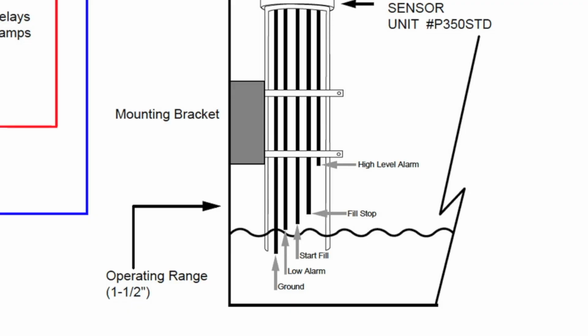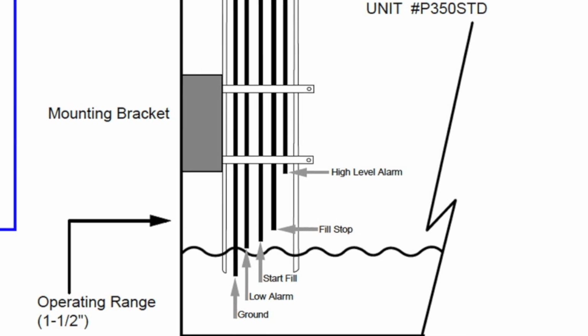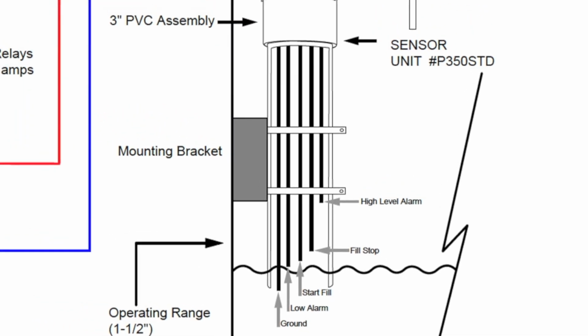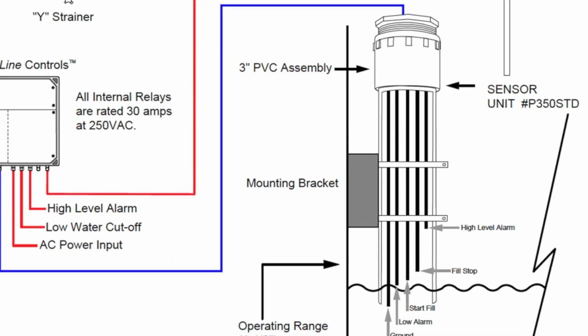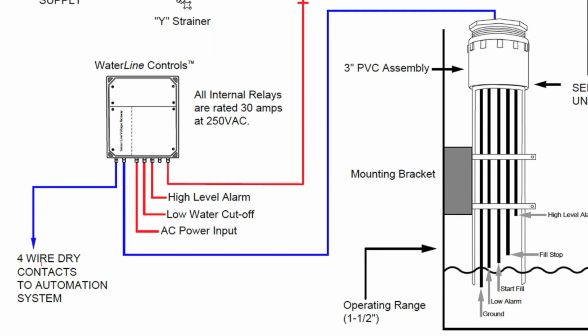The reference pin is the longest pin, and the first pin is a low alarm, which is equal to or a little bit shorter than that reference pin. Then there's a fill start switch, a little bit higher than that one, a fill stop that's higher than that one, and a high alarm that's higher than that one. Each of those set points is measured in this controller, and when it activates on that set point, a light turns on, and then a relay turns on that activates the valve. Relays can be used to activate audible or visual alarms at the site, and there's another set of dry contacts that go to the building automation, so you can electronically see all that action happening.